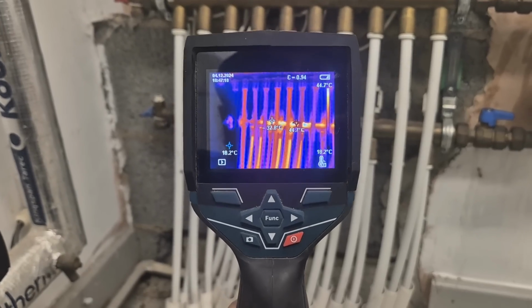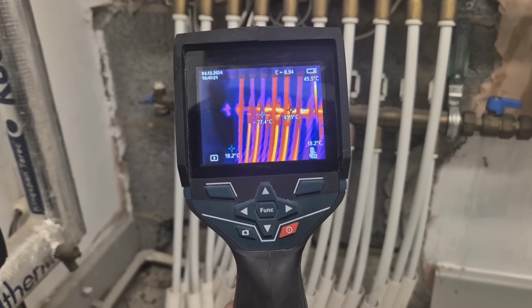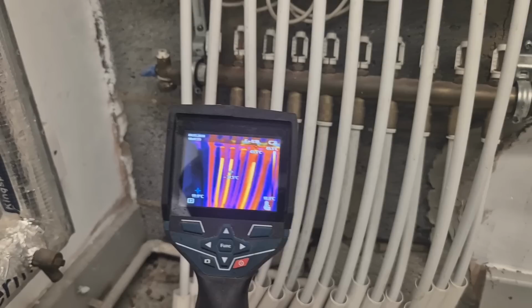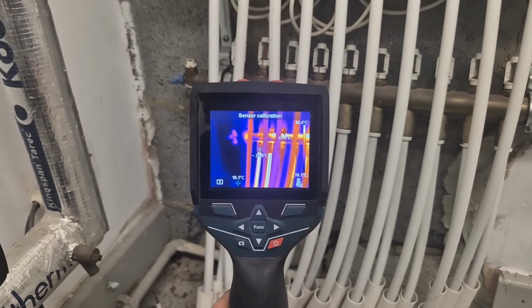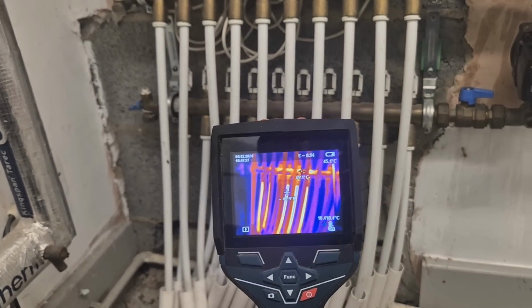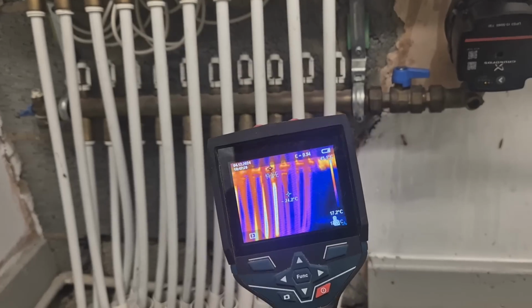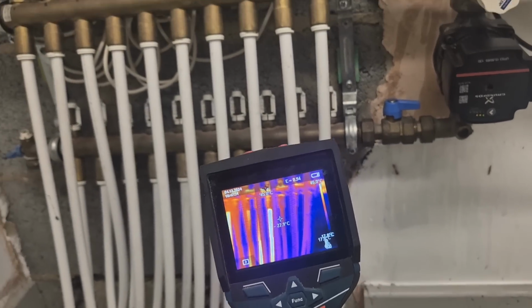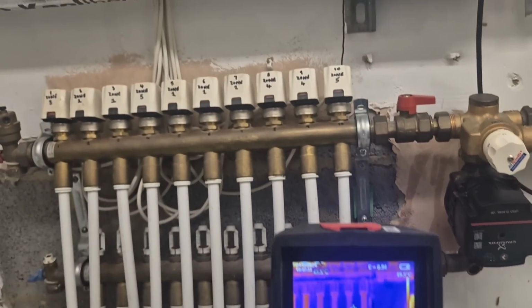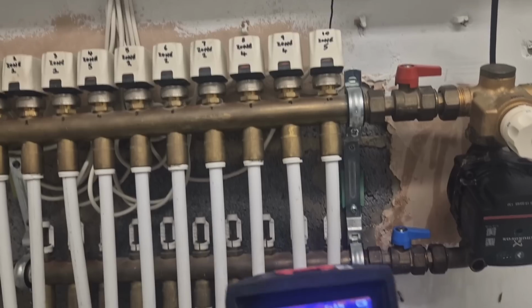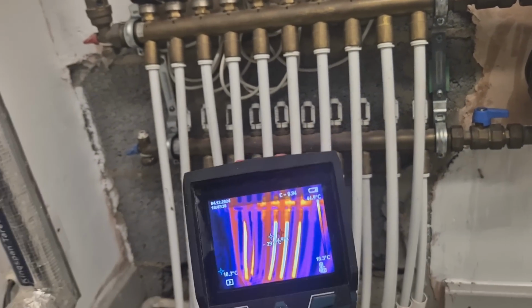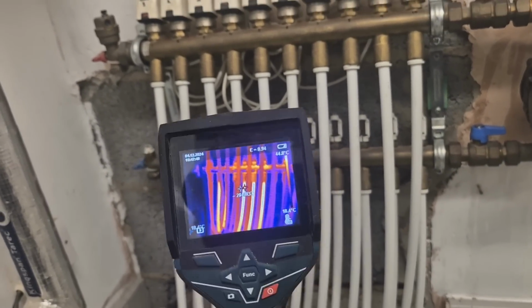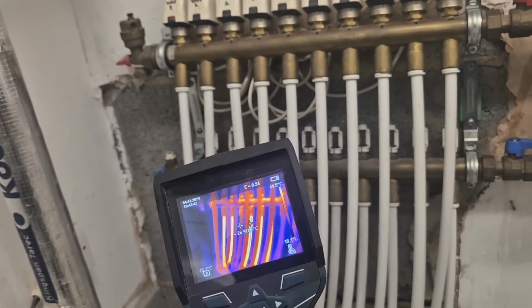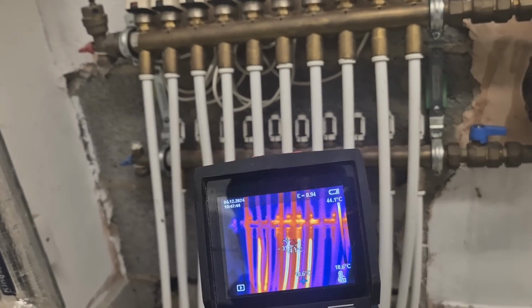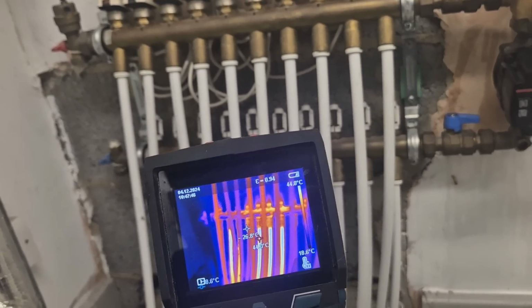Right, it's been about 10 minutes and they're all starting to come on. You can see the pipes at the back, and so the front one's the return on these. So we'll go and check that loop inside. See the back pipes, that one. Zone 4 might just be shutting off again actually. Zone 4 is shutting off. But all the others are working. It is quite warm in the building, so the call out was only one room not working. It just turned out to be half of it. So I think it was that one, but we'll go and check inside.